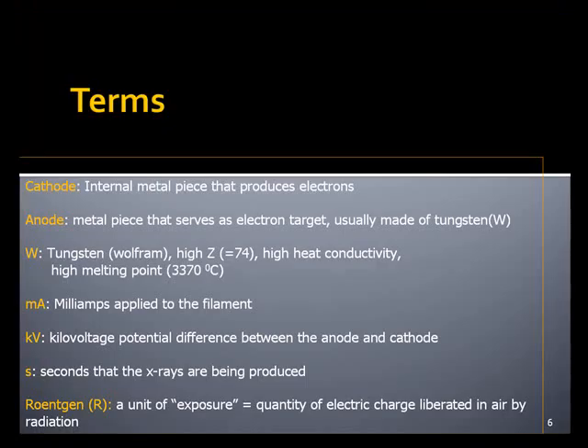Cathode: the internal metal piece that produces electrons. It's usually in the form of a little spring, like inside a light bulb — a source of electrons in an X-ray tube. The anode is a metal piece usually made of tungsten — W stands for Wolfram, a German word — that serves as an electron target. Anodes are high Z, atomic number 74, and have high heat conductivity so they don't soak up heat. Tungsten has a high melting point of 3,370 degrees Celsius. Milliamps is the current applied to the filament — one thousandth of an amp. Kilovoltage is the potential difference between the anode and the cathode, which accelerates the electrons from the filament to the anode.